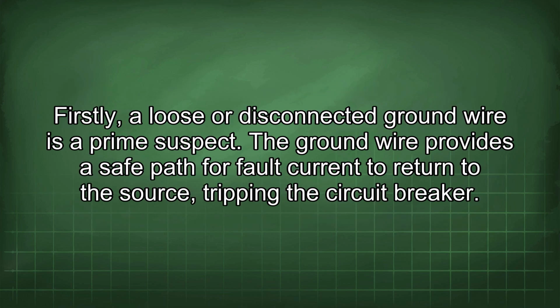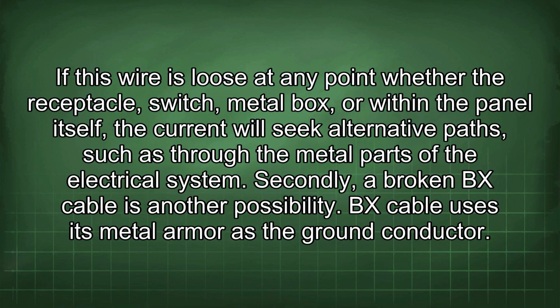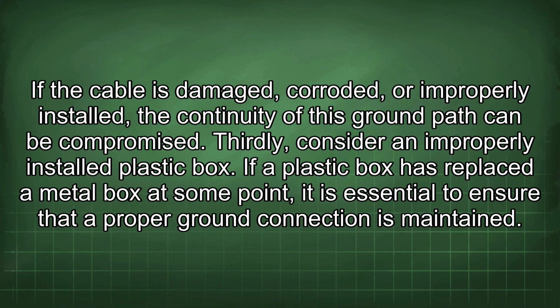Firstly, a loose or disconnected ground wire is a prime suspect. The ground wire provides a safe path for fault current to return to the source, tripping the circuit breaker. If this wire is loose at any point, whether the receptacle, switch, metal box, or within the panel itself, the current will seek alternative paths, such as through the metal parts of the electrical system. Secondly, a broken BX cable is another possibility. BX cable uses its metal armor as the ground conductor. If the cable is damaged, corroded, or improperly installed, the continuity of this ground path can be compromised.